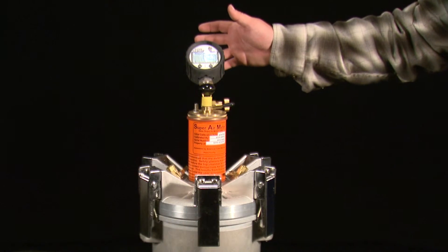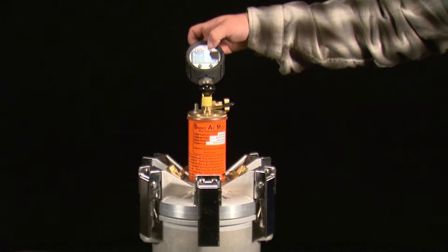Turn the meter onto PSI mode and inflate the top chamber to 45 PSI and let it sit for about 20 minutes.